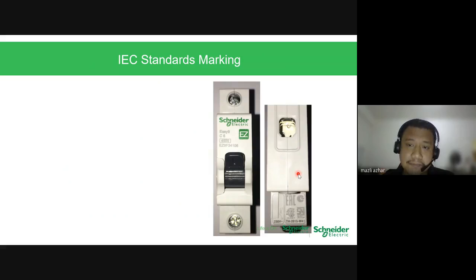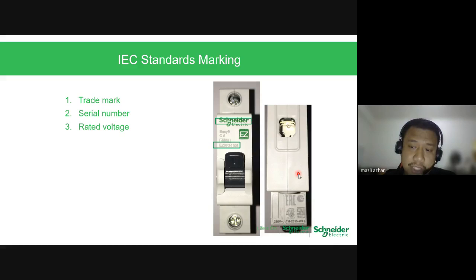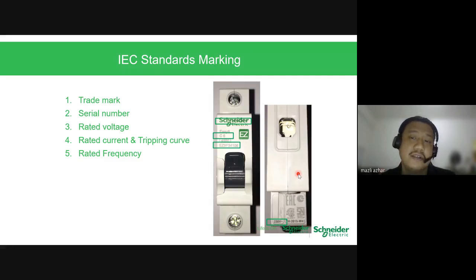So IEC standard marking, okay, this is a basic look of an MCB. All right. So we have trademarks. Each of the brands has trademarks. You have a serial number or reference number. Rated voltage, you can see here because this one is single phase. Rated current and tripping curve, you can see there C6 is a C curve 6 amp. Rated frequency is not stated here because it follows the Malaysian frequency, 50 or 60 Hz. If it's not 50 or 60, then the manufacturer has to declare it on the product itself. Short circuit capacity, you can see here 4,500. You can go up to 10,000, 20,000.